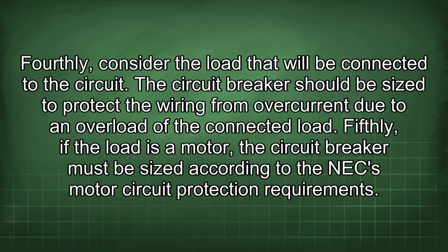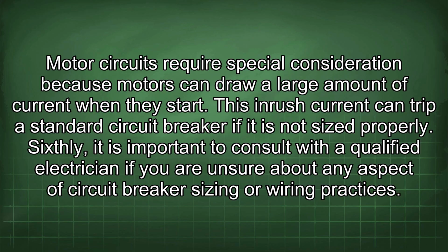Fourthly, consider the load that will be connected to the circuit. The circuit breaker should be sized to protect the wiring from overcurrent due to an overload of the connected load. Fifthly, if the load is a motor, the circuit breaker must be sized according to the NEC motor circuit protection requirements. Motor circuits require special consideration because motors can draw a larger amount of current when they start. This inrush current can trip a standard circuit breaker if it is not sized properly.